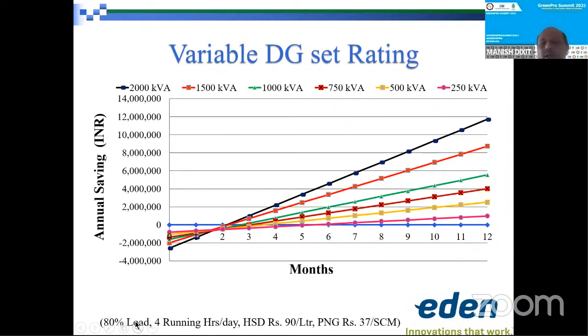For the same engine, say a 1000 kVA engine with the same fuel cost, how does my saving change? As load increased from 50 to 65 to 80 to 90, my savings kept increasing. Beyond the sweet spot, I had more diesel than gas, and therefore my savings had dropped, but I'm still not getting any derating on the engine.